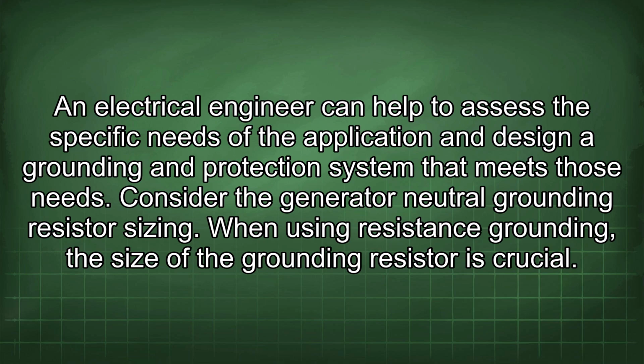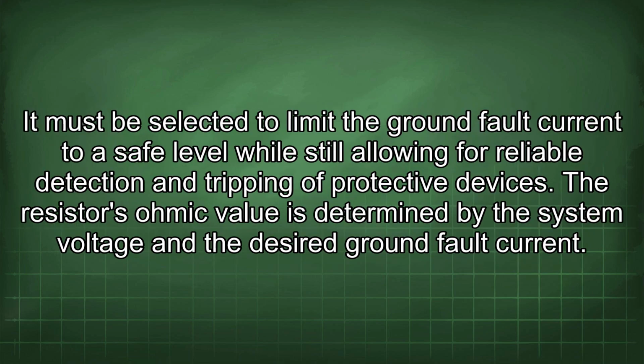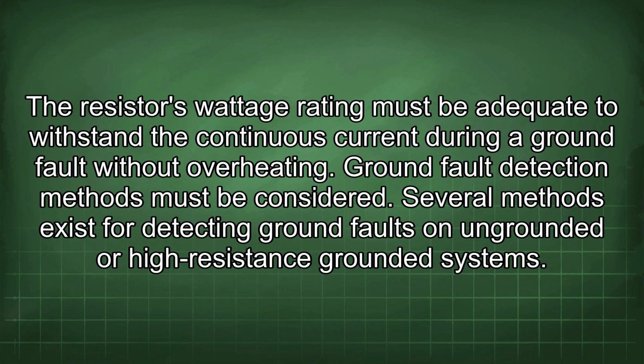When using resistance grounding, the size of the grounding resistor is crucial. It must be selected to limit the ground fault current to a safe level while still allowing for reliable detection and tripping of protective devices. The resistor's ohmic value is determined by the system voltage and the desired ground fault current. The resistor's wattage rating must be adequate to withstand the continuous current during a ground fault without overheating.